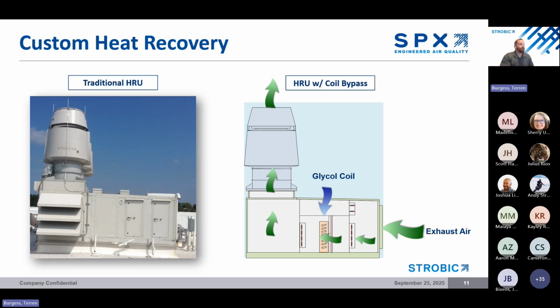So that's where heat recovery is going to come into play, and a properly designed heat recovery system allows us to capture a large portion of that heating or cooling energy from the exhaust stream and transfer that back into the incoming fresh air. Right, the two streams don't mix. This is a runaround loop, so safety always comes first, but energy can still be exchanged through these systems.